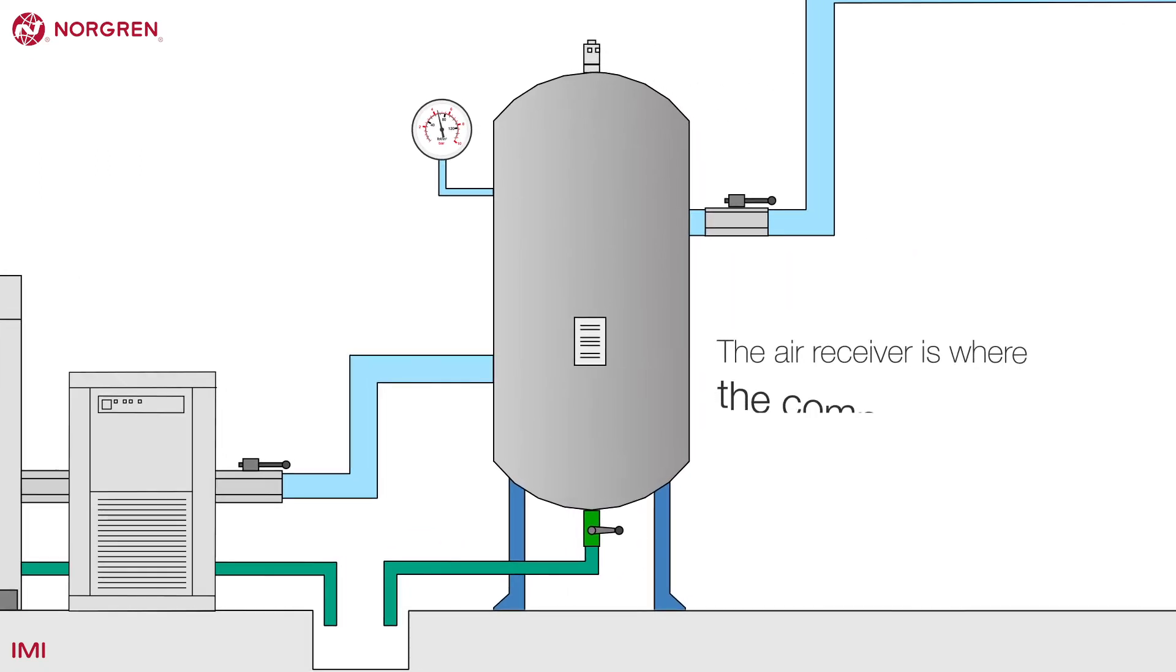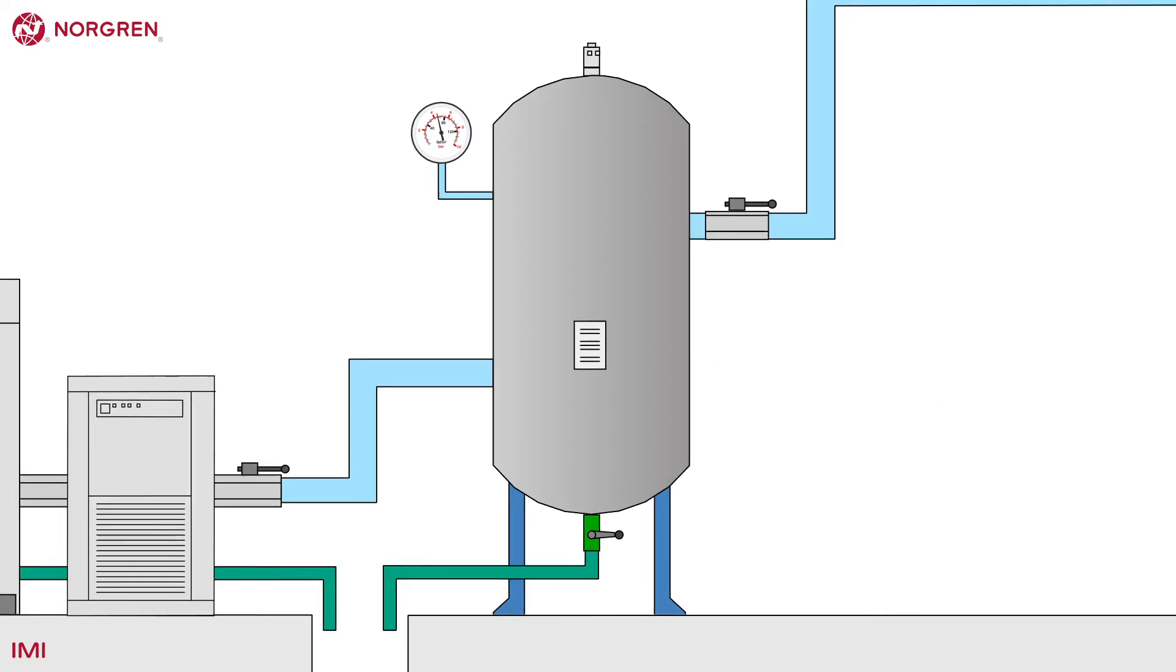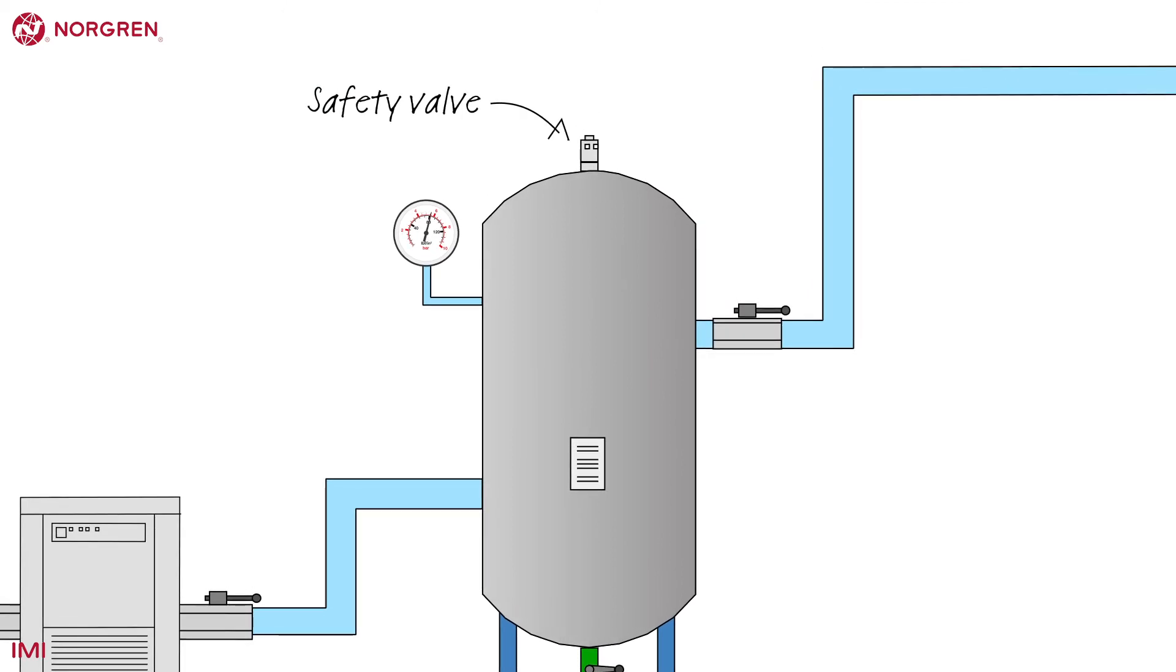The air receiver is where the compressed air is stored. Think of it as a battery. It's where the energy is stored. The safety valve will release air if the pressure rises above the set pressure, for example 10 bar. The pressure gauge displays the pressure inside the tank.